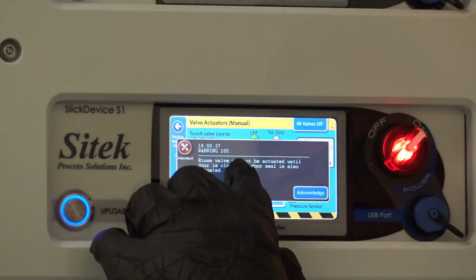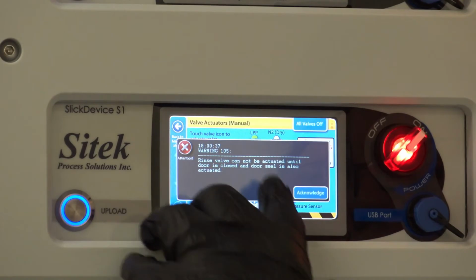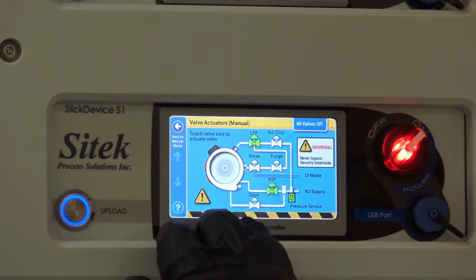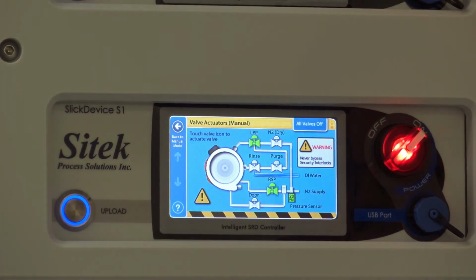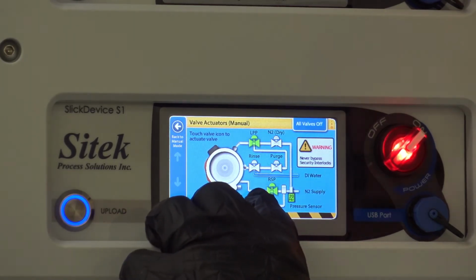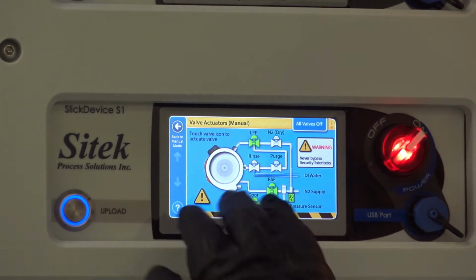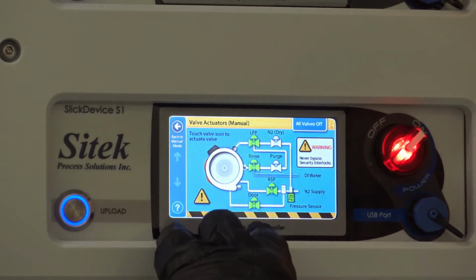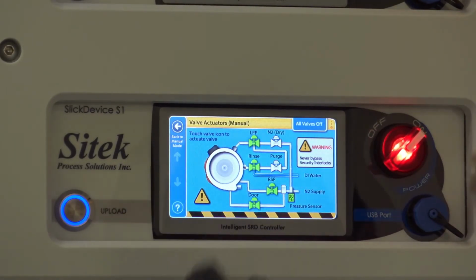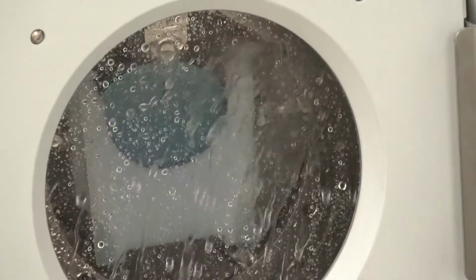You know why? Rinse valve cannot be activated until the door is closed and seal is also activated. So it's saying, okay, door is closed. Oops, I'm sorry, down here. Okay, door is closed. I'm going to lock the door now. I can't open it. It's green. Now when I hit rinse, if you look down below, because again I'm doing the bottom rinser dryer, notice how it's manually rinsing now. And I'm going to hit turn it off, and it ends.